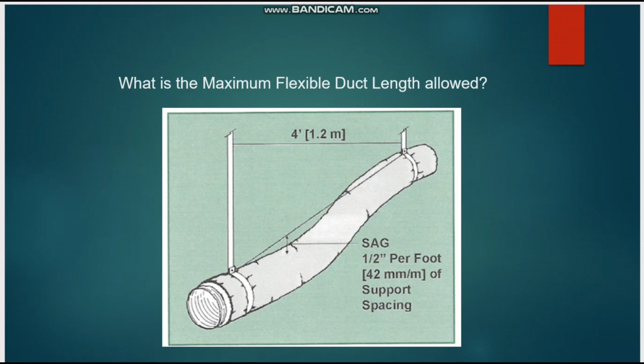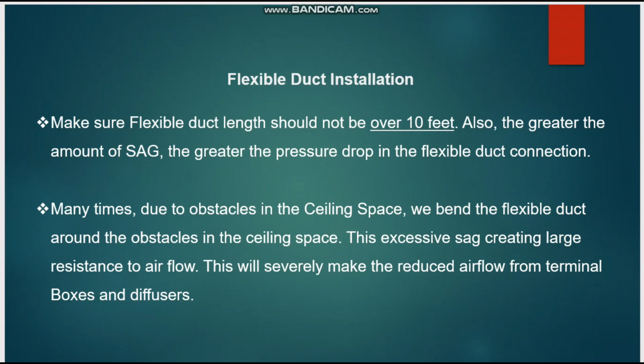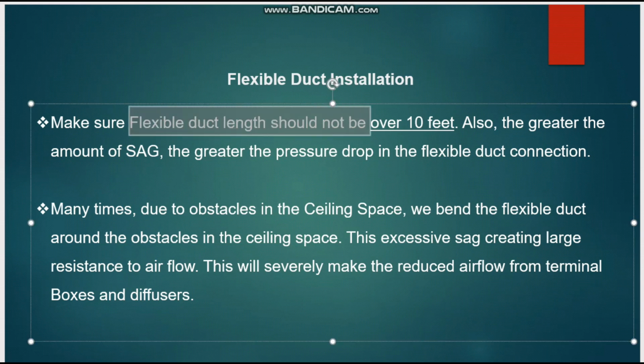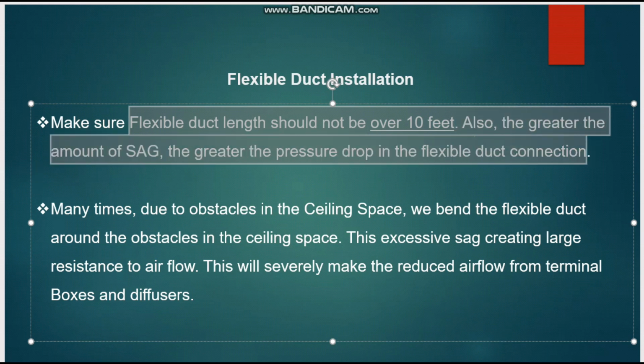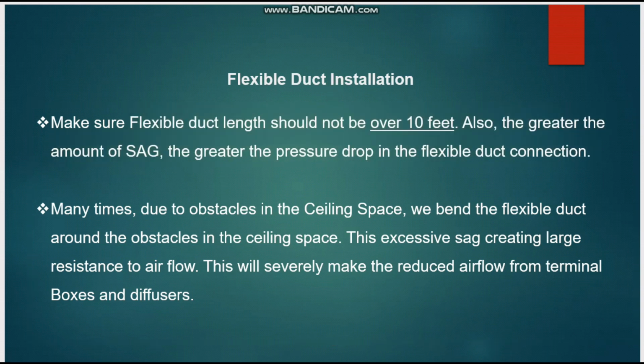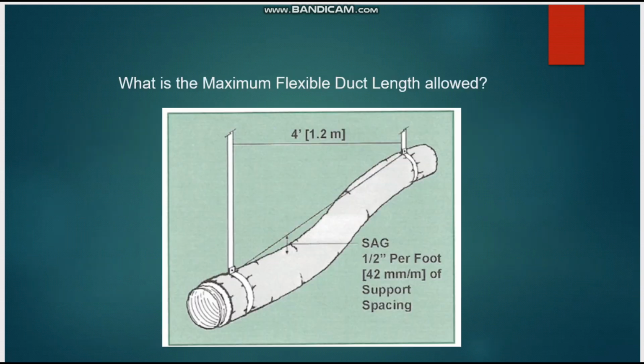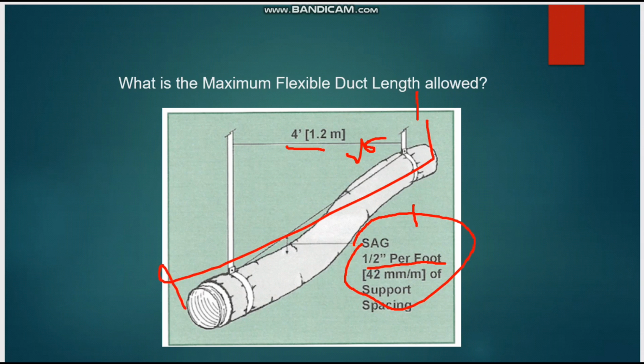What is the maximum flexible duct length allowed? So if you see here, make sure the flexible duct length should not be over 10 feet. And also the greater the amount of sag, the greater the pressure drop in the flexible connection. Regarding the sag and the distance between the supports, I explained in the last video. The sag is the deflection, and half inch per foot is allowed. In 1 foot, a maximum of half inch deflection is allowed for the support, and also spacing of 4 feet is allowed, and the maximum length of the flexible duct is 10 feet. Between this point and this point, it should not exceed 10 feet.